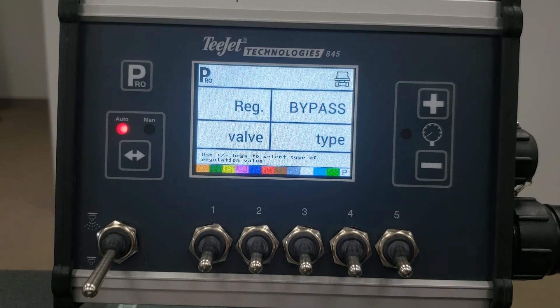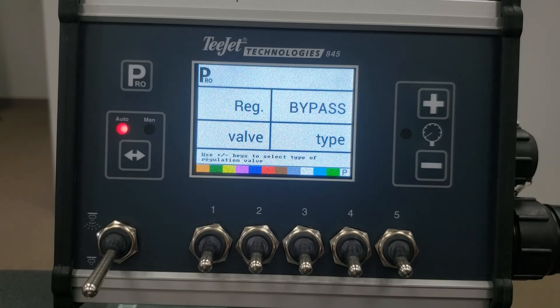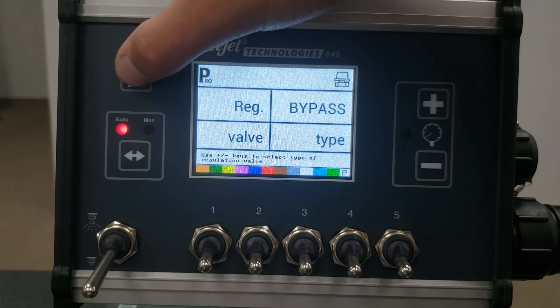The next step is where you set the type of regulating valve on your machine. Choices are bypass, throttling, and PWM. Bypass regulation is when the regulating valve is placed in a return line to the tank. Throttling regulation is when the regulating valve is placed in the main flow line. PWM regulation is when you are controlling the flow in the product line by controlling the speed of the pump via a hydraulic valve. The default is bypass. Press the Pro key to move to the next step.